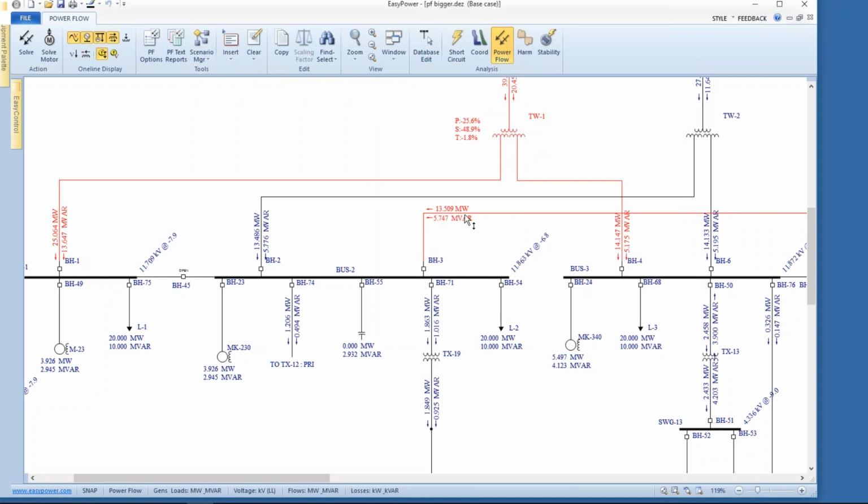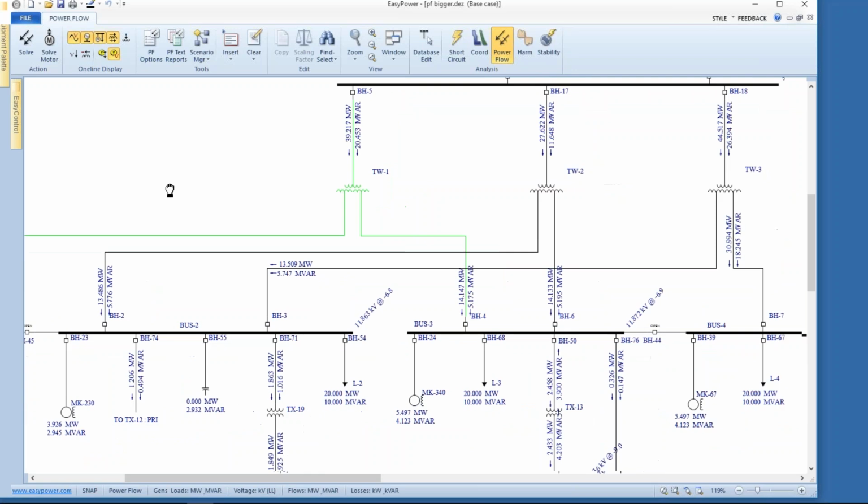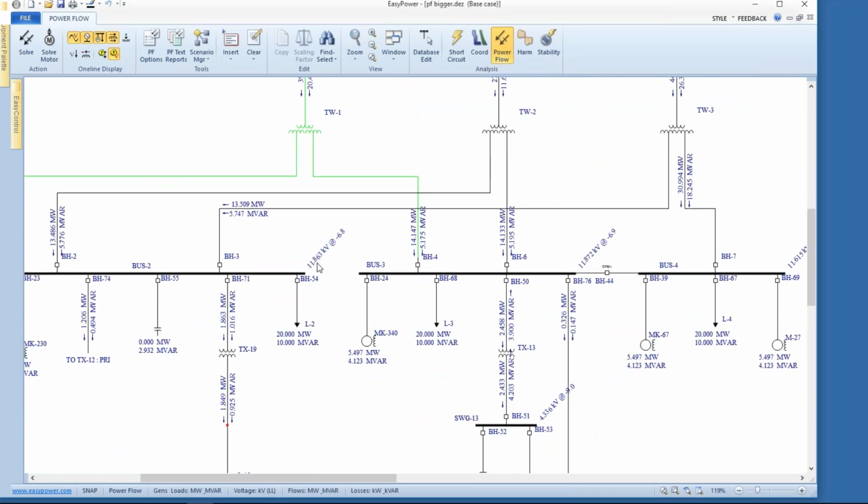And so that's what's generating these indications in red. And then finally, the voltage violations. We're not seeing anything that's giving us a voltage violation just of itself, which is a 10% overload.